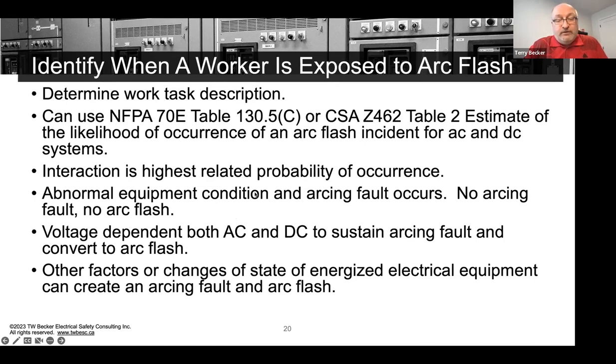But we can get an abnormal arcing fault without interaction. It has happened. It does happen. I talk about likely occurrence for either of these, and they're low likelihood already with this additional oversight. And if you apply this information and train your workers and have it all defined in an electrical safety program where you implement specific policies, practice and procedure requirements, the likelihood drives down even further, right? So abnormal equipment conditions, because we create it by removing a bolt-on cover energized or opening a hinged door, or for instance, water gets into the electrical equipment, right? Some form of contamination can cause that abnormal arcing fault between conductors because we compromise that gap, right? The air gap is insulation. When we compromise it with us or something else that can conduct and we get it too narrow and the voltage is high enough, three phase, we can sustain an abnormal arcing fault, and it becomes an arc flash, all right?